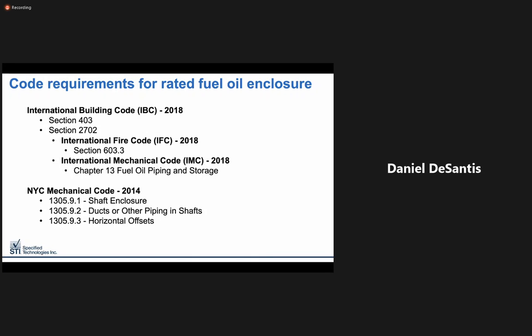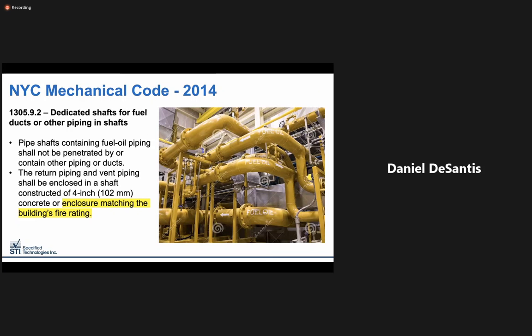Let's take a closer look at the New York City Building Code on fuel oil line. Under the 2014 NYC Mechanical Code, dedicated shafts for fuel oil should not be penetrated by or shared with other piping and ductwork. Completely dedicated shafts are required. Chapter 13 speaks about the fuel oil piping requirements and states that fuel oil return and vent piping must be enclosed in a shaft of 4-inch thick concrete or an enclosure that matches the building's fire rating. In most cases, this will be a 2-hour enclosure, but your rating may vary. Please consult with the AHJ of your project for the exact requirement.